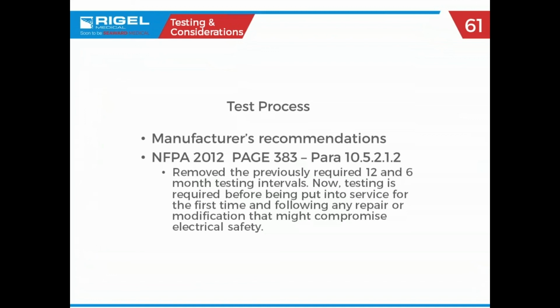Test process kind of goes to the question before, manufacturer's recommendations. Paragraph 10.5.2 in NFPA 99, which has 15 chapters, some dealing with gas, chapter 6 dealing with electrical circuits. Chapter 10 is all about electrical safety. Safety testing is required before putting the device into service for the first time or following any repair or modification that might compromise patient safety. So they're really starting to open up the window as to how often electrical safety testing has to be done, but it all comes back to hospital process.